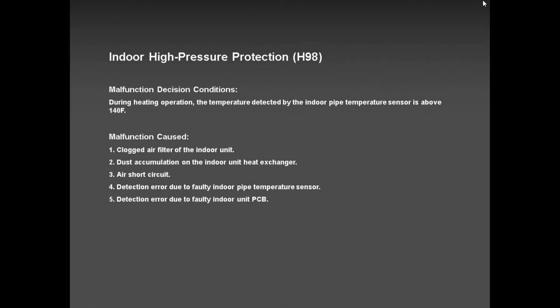H97. I have never seen an H97 that killed the board, that blew off the outdoor PCB. I know some competitors have this issue. When they have an outdoor fan motor defective due to snow or ice, it takes out the outdoor board as well. Ours, so far, touch wood, it's only the fan blade that got stopped. You switch off the unit, remove all the ice, thaw all the ice, and you're up and running.